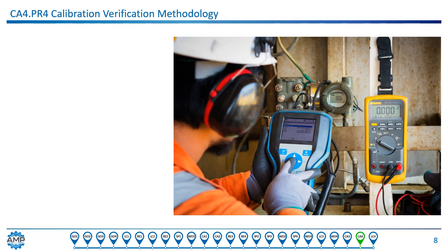Calibration verification creates guidelines for verifying instrument calibration outside of set intervals. Calibration intervals are great, but there are other events that require a calibration to be performed. The calibration program must identify those events or circumstances and make provision for how they are triggered and how they interface with the regular calibration tracking and information processes.